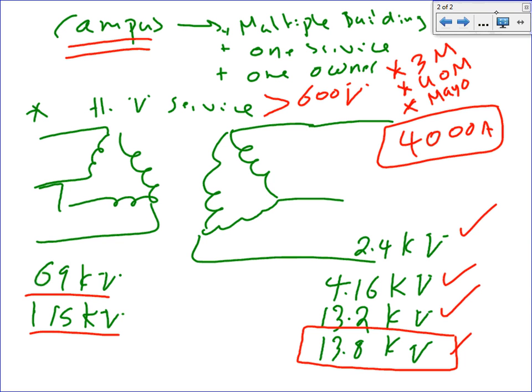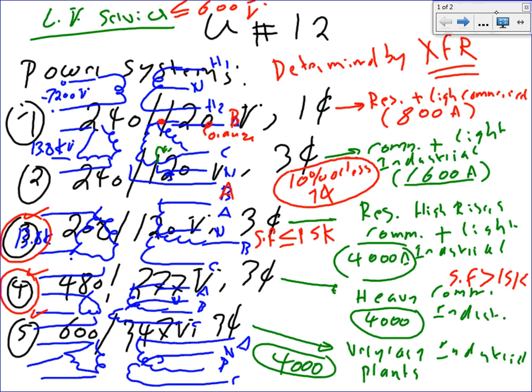You know, you take this transformer, move it 4 miles to a different building through the cable, and then you have a substation where you transform it back again to 480-277 most of the time, or 208/120. So you take these feeders, guys, and you transform them down into one of these three services. Here's where 13.8 comes in, and then you dump this power into your building as one of the last 3 forms, 3, 4, or 5. So how do they generate the neutral? Do they just go off the ground then? Yeah, you create your own neutral.